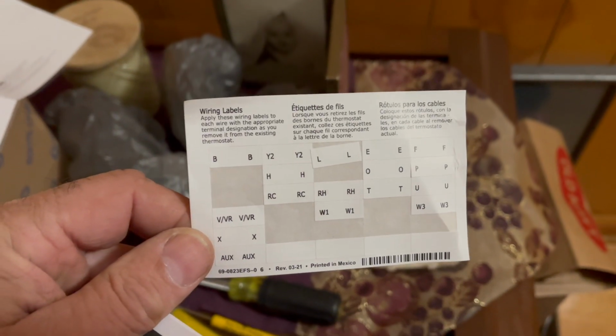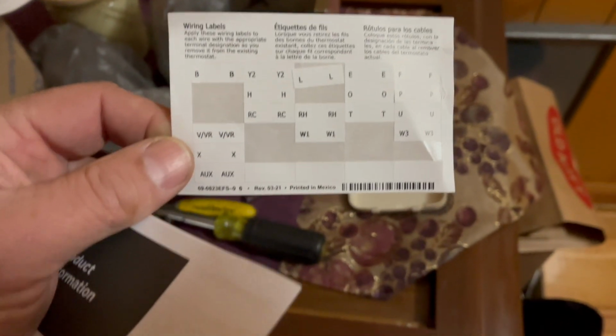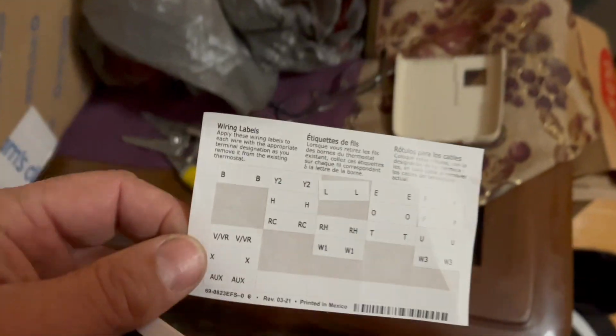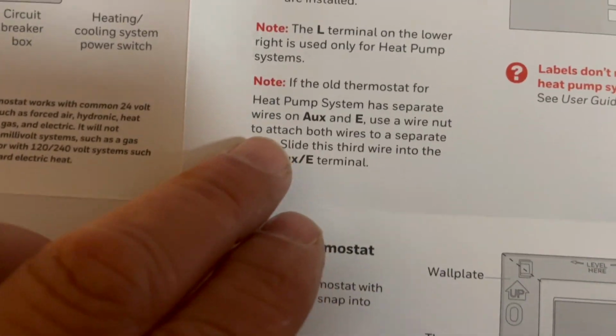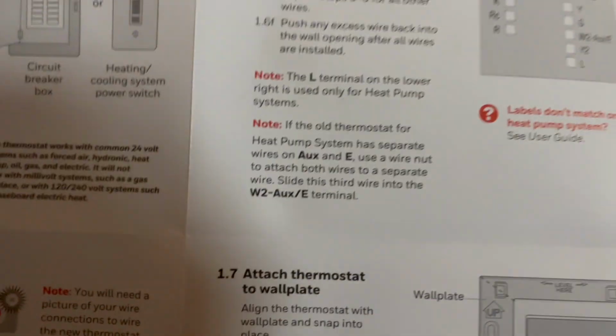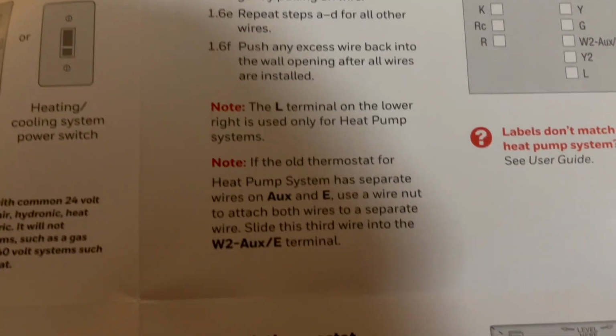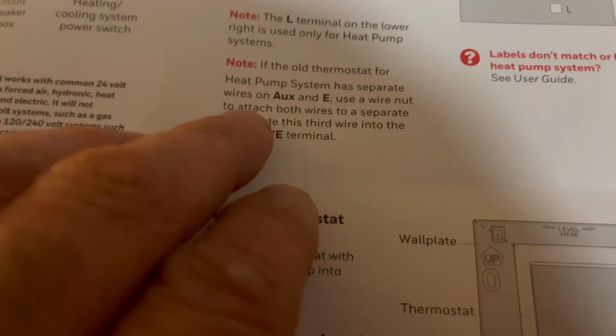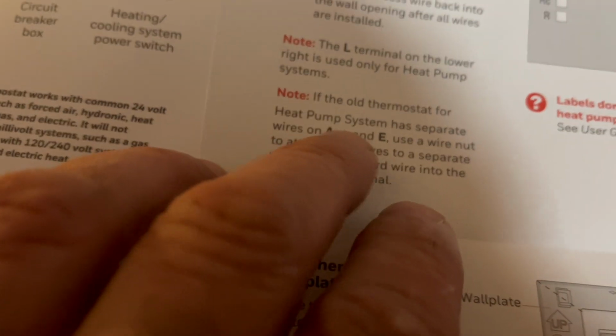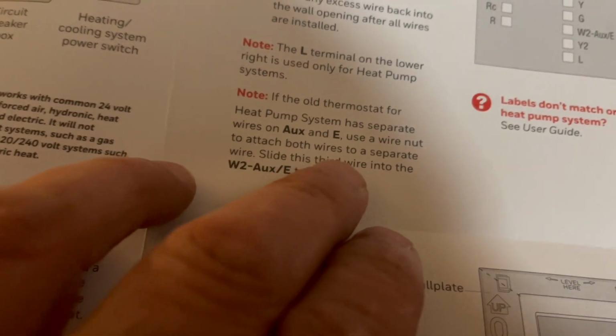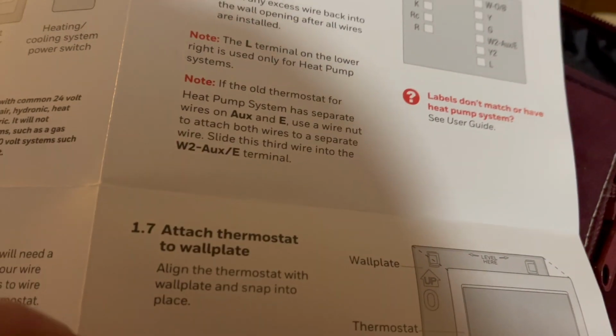Oh yeah, somebody's been here before. Here's the little stickers that come in the box that you're supposed to put on the wires, so maybe somebody did try to install it. One thing I always have a question about on these different thermostats is the auxiliary and E terminals. Sometimes they have two separate terminals and you have to put a jumper, which looks like they did give us for some reason. But this one says if your old one has both, you have to use a wire nut to attach them together, so we're good. We only have the one.